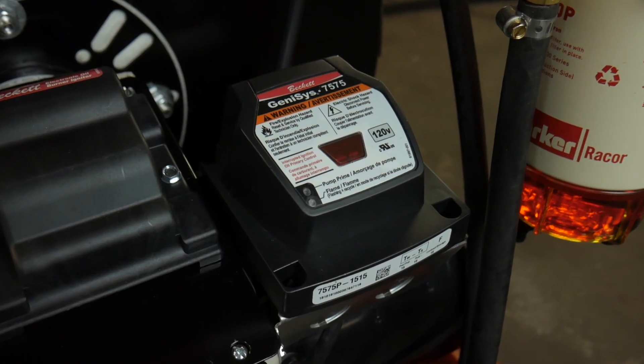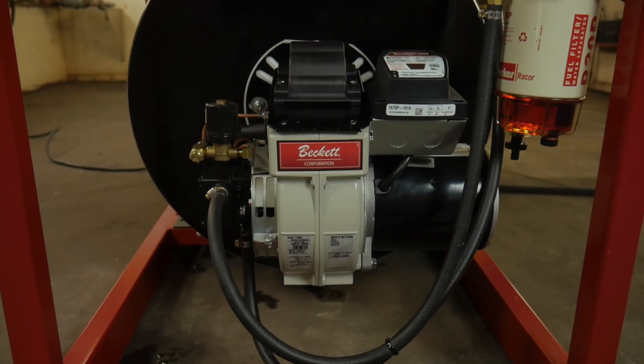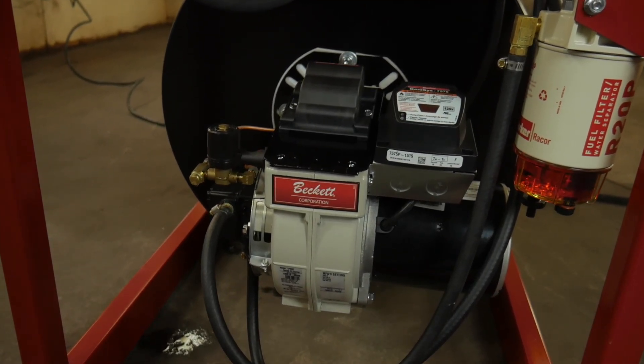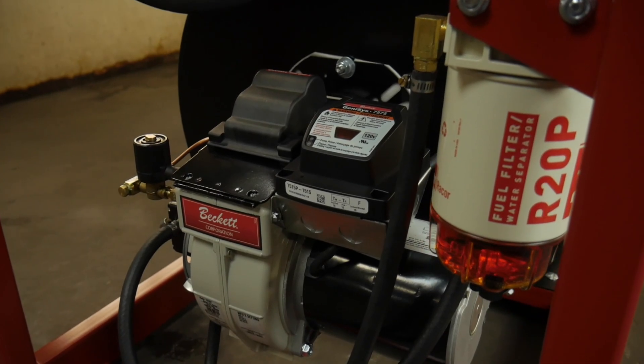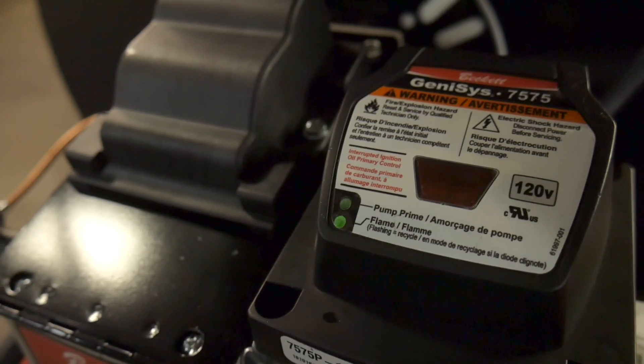For pressure washers that meet the UL 1776 standards, a burner control like the Beckett GeniSys 7575 must be used. The function of the burner control is to manage the proper startup sequence of the burner and to monitor burner parameters. The burner control is located above the blower motor. Under normal operation, the green LED will be illuminated.